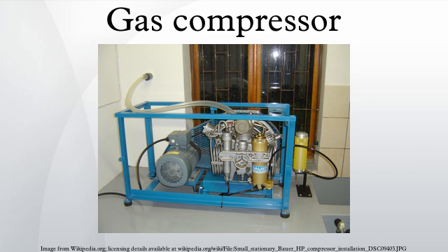In the case of small reciprocating compressors, the compressor flywheel may drive a cooling fan that directs ambient air across the intercooler of a 2 or more stage compressor. Because rotary screw compressors can make use of cooling lubricant to remove the heat of compression, they very often exceed a 9-to-1 compression ratio. For instance, in a typical diving compressor the air is compressed in 3 stages. If each stage has a compression ratio of 7-to-1, the compressor can output 343 times atmospheric pressure.